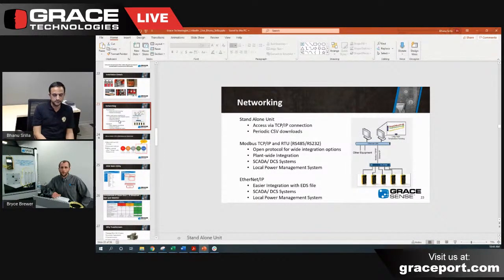Yeah, absolutely. The device has an RJ45 port at the top where you can easily put that into a switch, and then you have Ethernet/IP or Modbus TCP communication. So if you want to bring this into, say, a Rockwell ControlLogix system, we have an EDS file that makes it very easy—it brings in the tags fully named so you can bring that into your program and choose how to use those tags. It also has an onboard ability to do an output, so you can simply set up the alarm threshold and have it send a trigger to a stack light or into the control system.